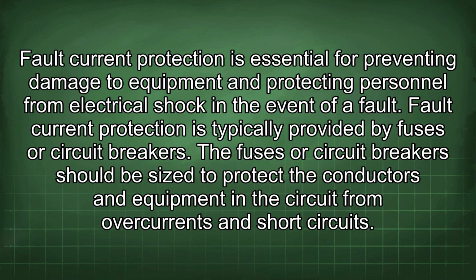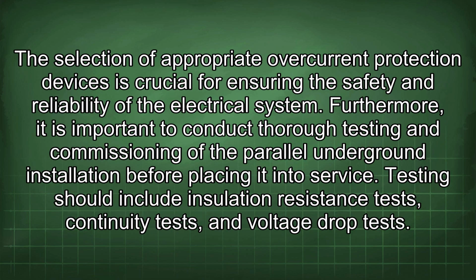Fault current protection is essential for preventing damage to equipment and protecting personnel from electrical shock in the event of a fault. Fault current protection is typically provided by fuses or circuit breakers. The fuses or circuit breakers should be sized to protect the conductors and equipment in the circuit from overcurrents and short circuits. The selection of appropriate overcurrent protection devices is crucial for ensuring the safety and reliability of the electrical system.